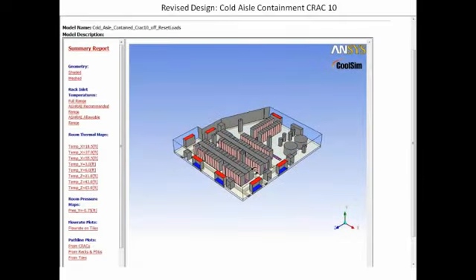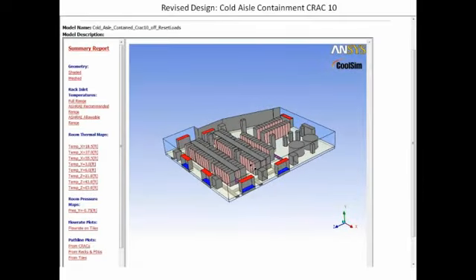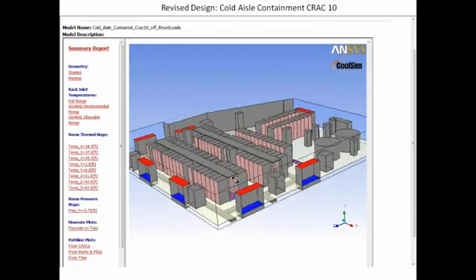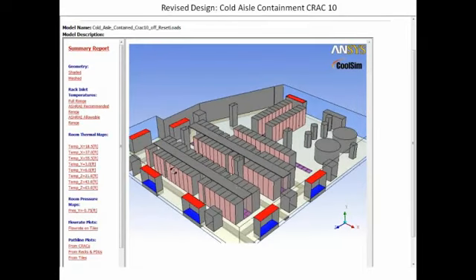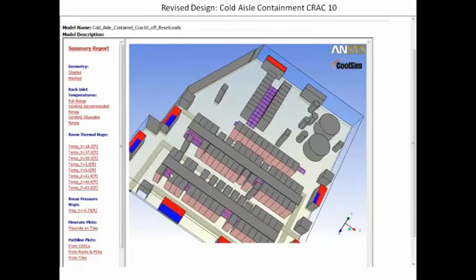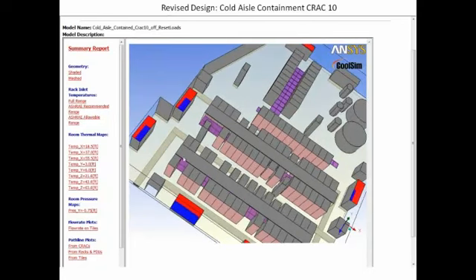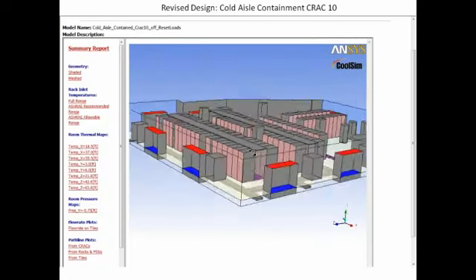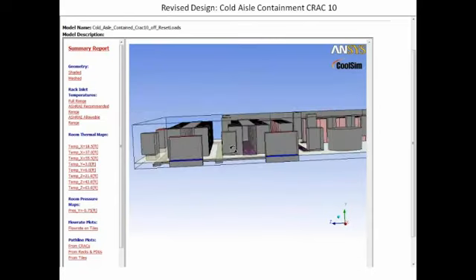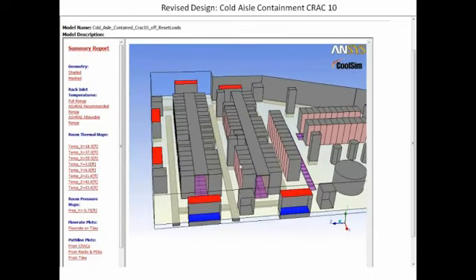So what we also did here, I made another run. I mean, this design was begging for cold aisle containment because we had recirculation occurring over here at this end of the room. And so I took 2 tiles out, kept the loads the same, put in cold aisle containment down at this end. These are assumed to be some kind of curtains over here.